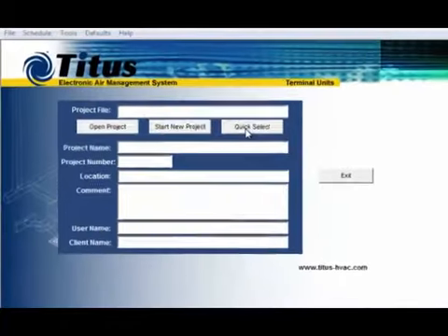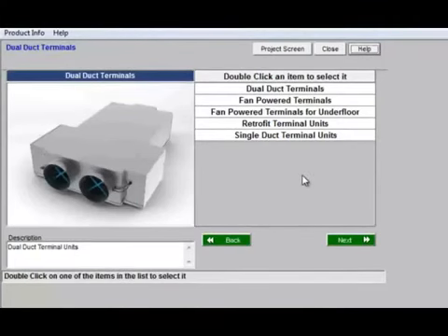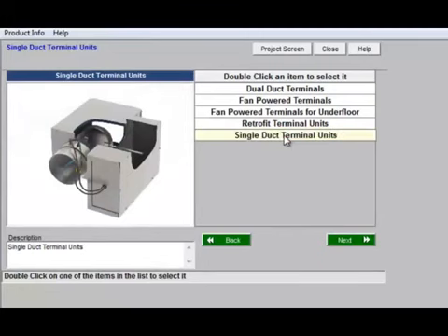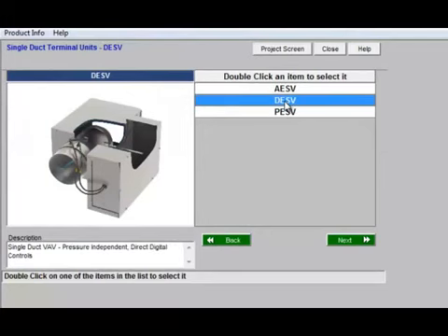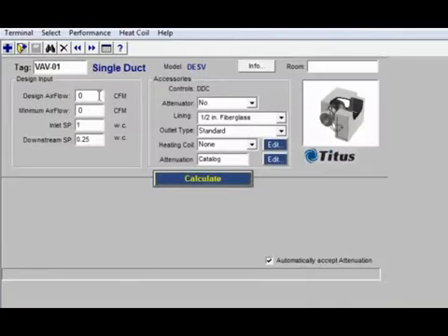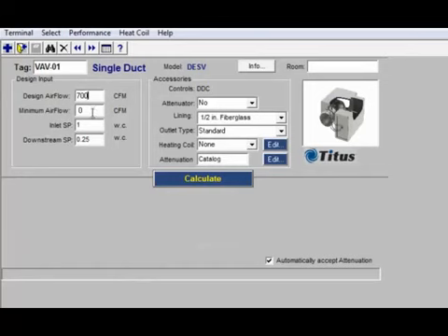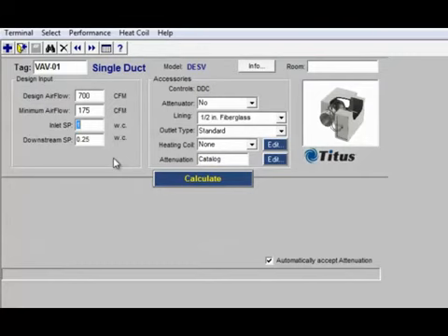Now let's look at how we do a selection on a single duct VAV box. We open our Titus selection program and I'm often working in quick select. Over here we have our choice of terminal unit and we're going to select a single duct. We've got our input screen. Let's say we want to have a design air flow of 700 CFM. Our minimum flow is usually going to be 20 to 25%, so about 175 CFM. Our inlet static pressure defaults to one inch of static pressure, which is pretty normal for a single duct VAV. Our downstream static pressure defaults to a quarter inch, which is a good conservative number to use for making selections — this is the downstream static pressure caused by the discharge duct work, takeoffs, balancing dampers, flex duct, and diffusers.